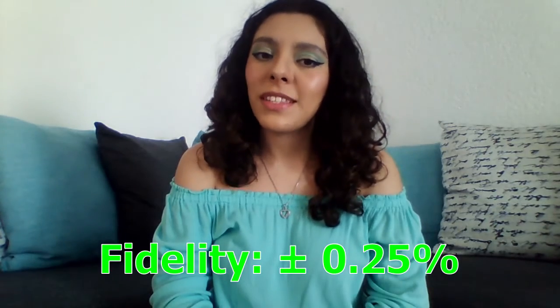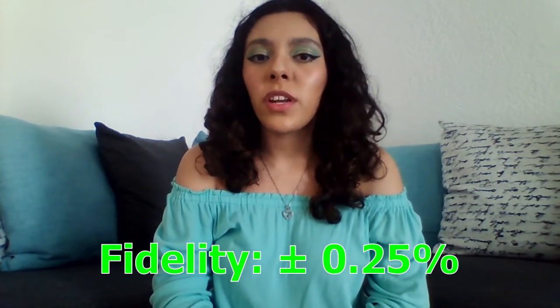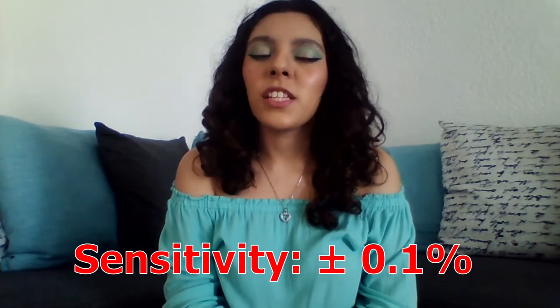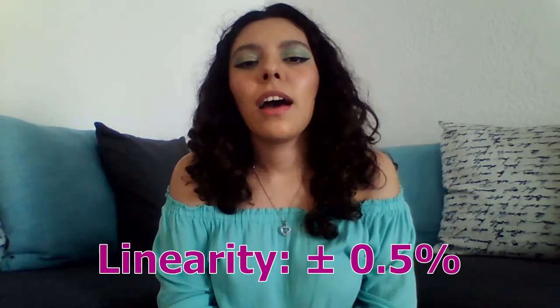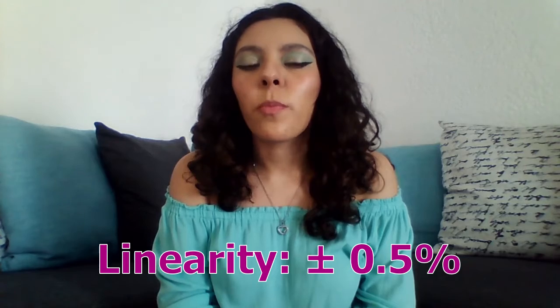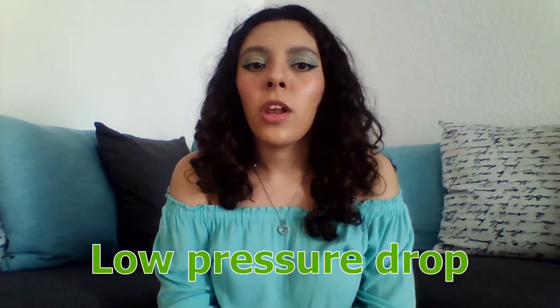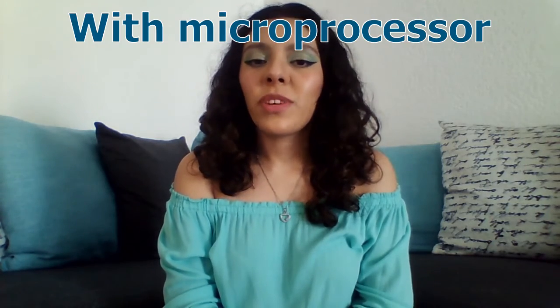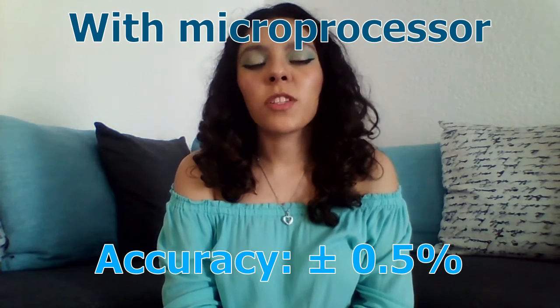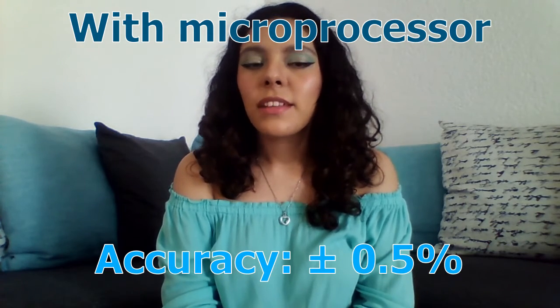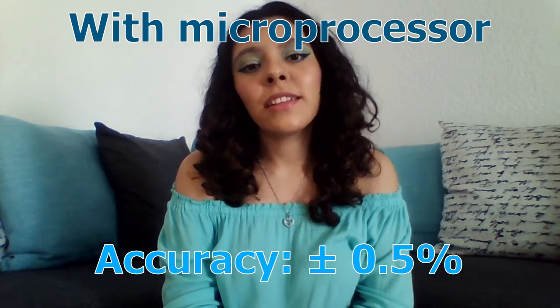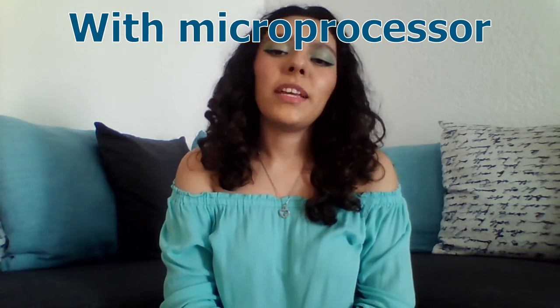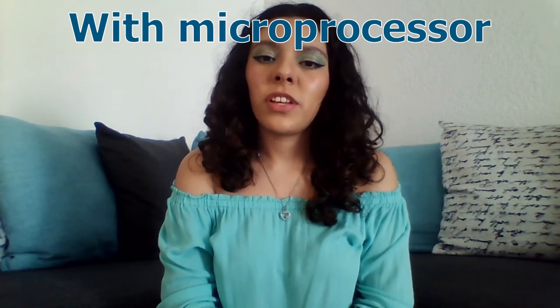The fidelity of the set is ±0.25%. Their sensitivity is ±0.1%, and their linearity is ±0.5%. And they have a low pressure drop. When a microprocessor is added, its accuracy becomes ±0.5% thanks to the high-frequency circuit and digital signal filtering, which eliminates interference from solid deposits in the pipeline.